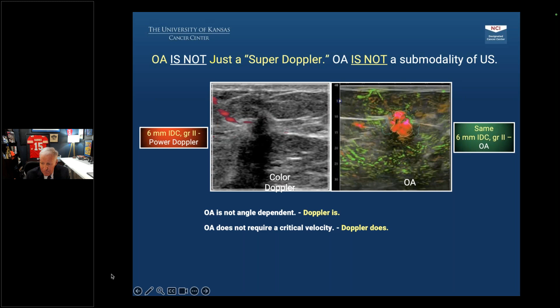What does that mean in practicality? Well, let's just say that a voxel is a millimeter. Because the contrast ratio in Doppler may be 1.5 to 1, if that vessel doesn't fill 90% of a voxel, it will not be detectable. On the other hand, OA can have a contrast ratio anywhere between 6 and 20. So let's just take the example of a contrast ratio of 20 to 1. That means that a vessel can only fill up 10% of the voxel, which is 100 microns in size, and still cause that voxel to light up with a 2 to 1 contrast ratio.